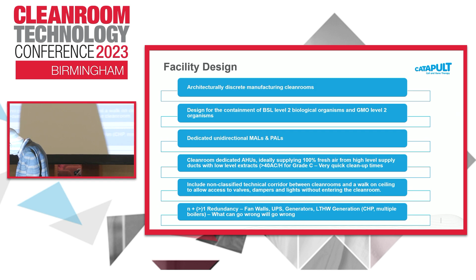Okay, facility design. So the clean rooms themselves need to be architecturally discrete, so self-contained production environments with all necessary support areas that can operate autonomously. The best designs I've seen is where there is some form of physical separation between those clean rooms. So, for example, you might have adjacent clean rooms with an uncontrolled technical corridor running between them that will allow engineers and maintenance staff access to utility plates from outside of the clean room. So that means that considerations for calibration, maintenance, repairs can be achieved without actually breaching the integrity of the clean room, disrupting operations and adding to downtime, which we'll want to avoid as best as possible.